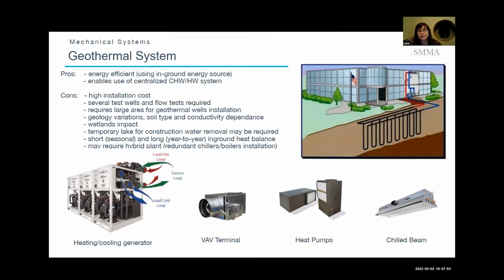Another factor to consider when we drill wells is when the groundwater is close to the surface, what to do with this groundwater, how we store it. Would we let this water go back into the ground? Eventually we have to treat this water. It could require a temporary lake or something to hold this volume, because once you start drilling, the water comes in at a very high rate. Another impact on a geothermal system is a wetland area, so the town will have to decide how close they would allow drilling near the wetlands.